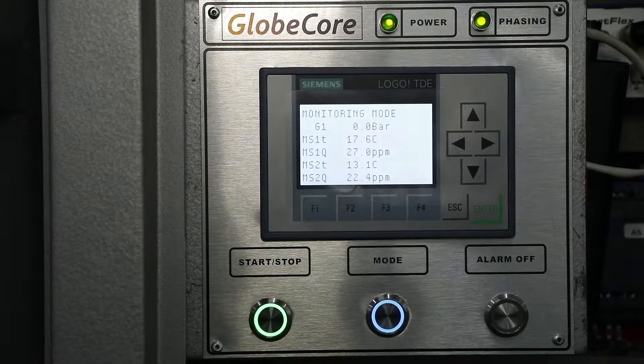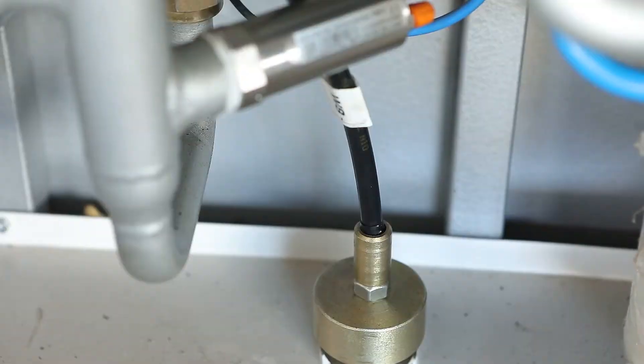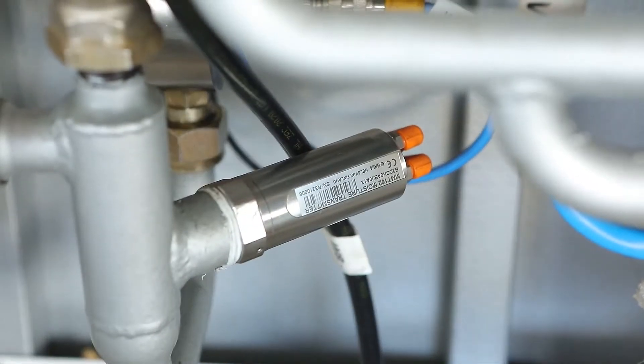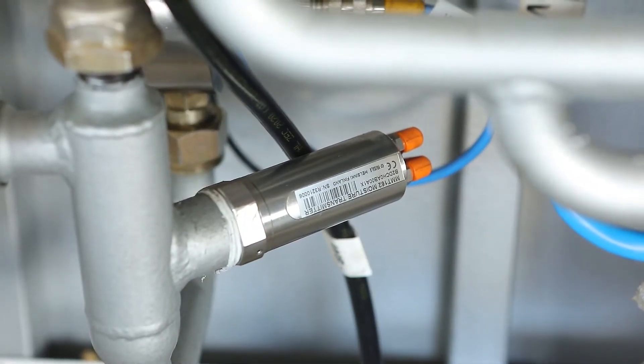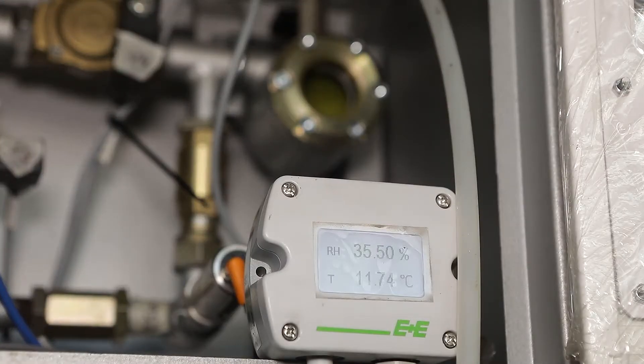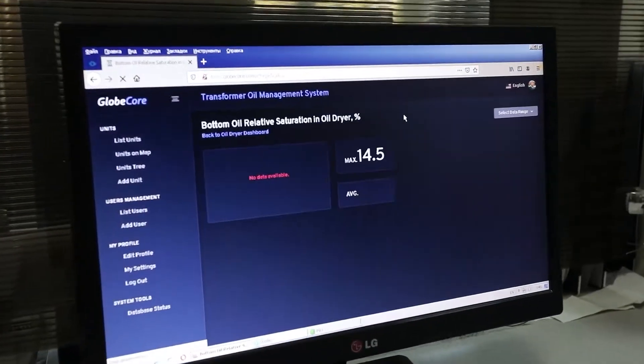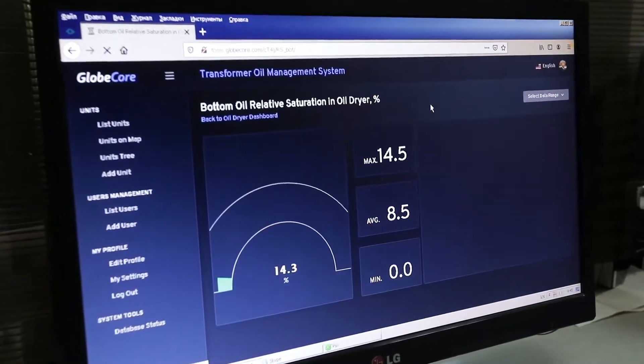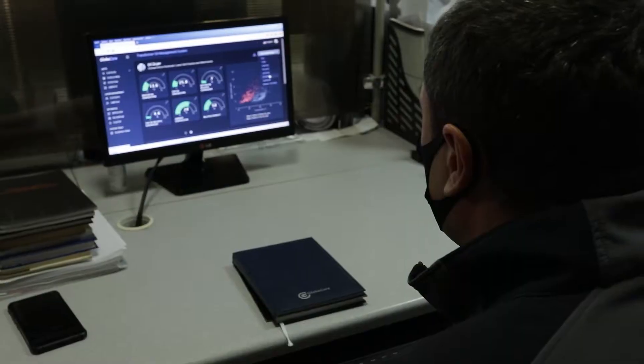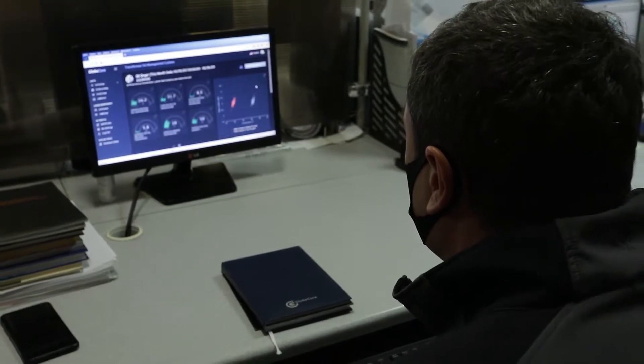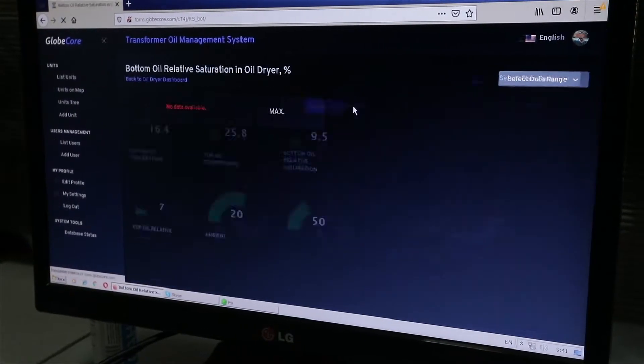In monitoring mode, the TOR system uses sensors to measure the oil temperature and water activity once a minute. These data are transmitted via the internet to a cloud server, where they are used to calculate the moisture content and the electric strength of the oil, the water content in solid insulation.